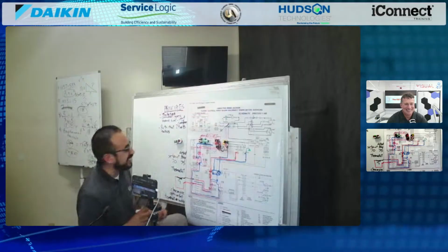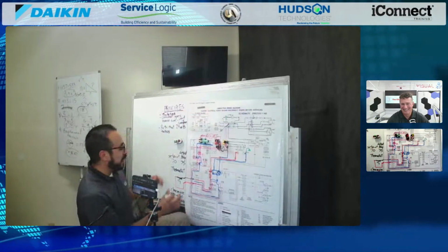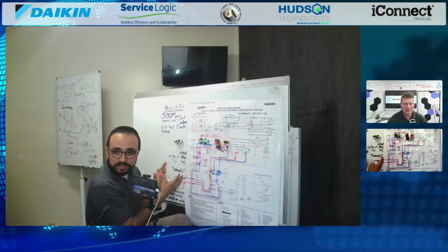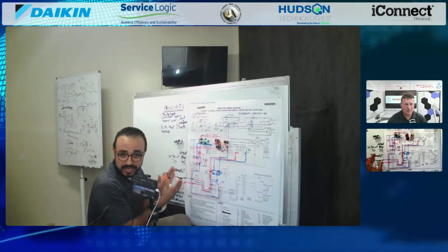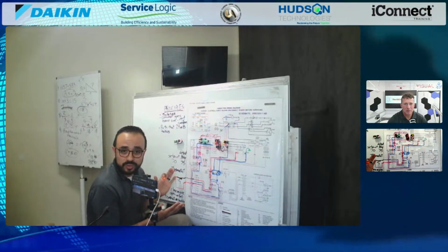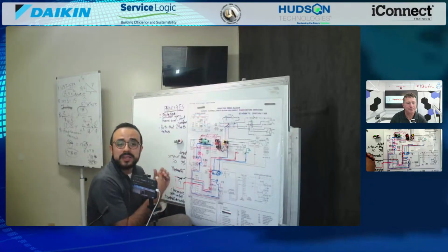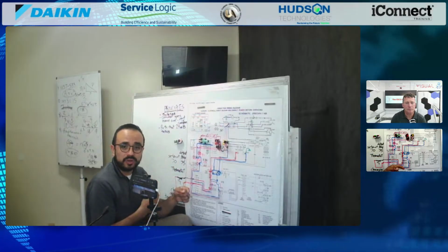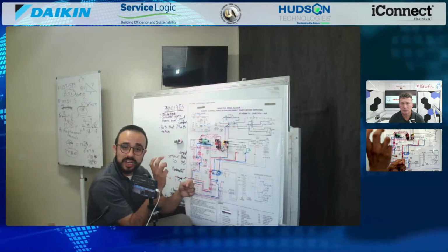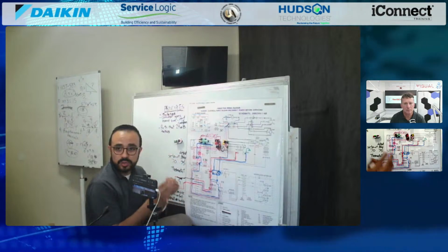Of course you got to program the thermostat for a heat pump. If you don't do that, it doesn't matter what the path is, you got to program it. In this case, it's a reversing valve for cooling, so you choose the letter O, not B. So O, reversing valve.